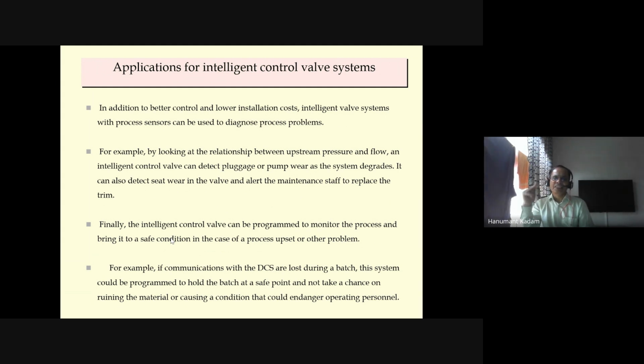Finally, the intelligent control valve can be programmed to monitor the process and bring it to a safe condition in the case of process upset or other problems. So you can have an interlock, or you can configure these Fieldbus valves for a safe condition. It means if the plant stops, the valve has to be closed, for example. It will automatically close the valve on a power trip or any other condition. Plant has tripped, the valve has to close.